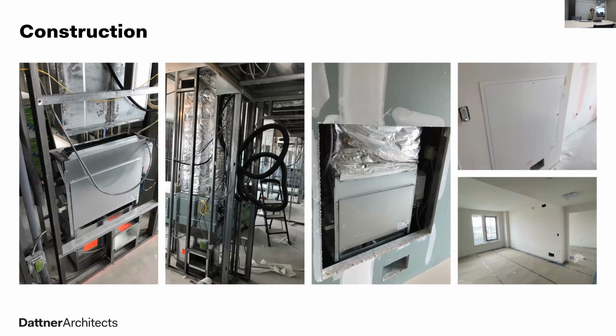So these are those floor mounted VRFs being installed. Passive house requires all return air to be ducted, so even though these units are made to use the wall as a plenum, we ended up needing to put small return ducts on the bottom of the units to meet that passive house requirement.